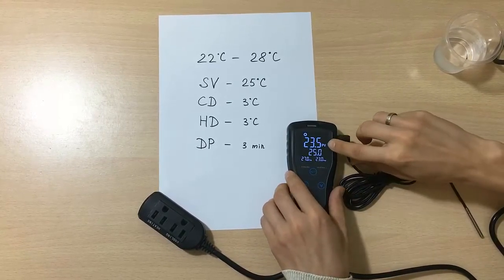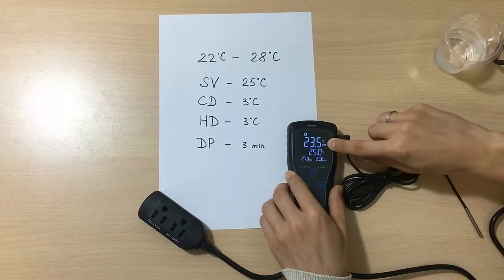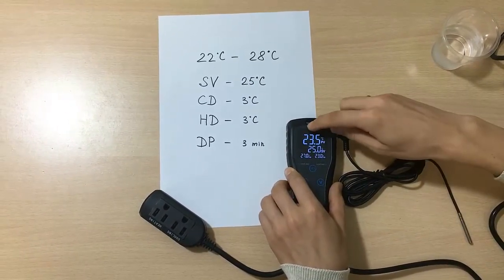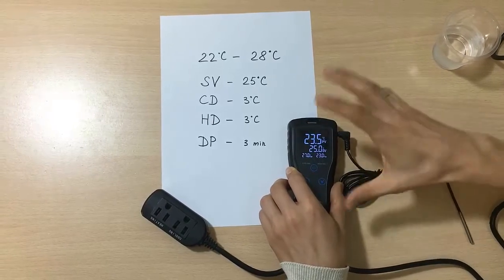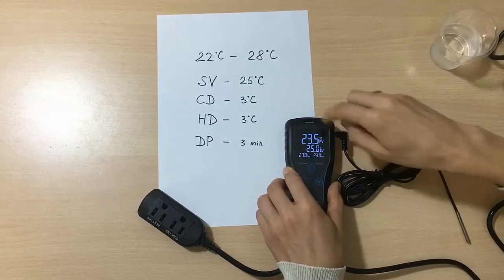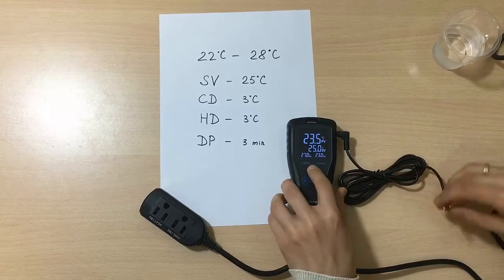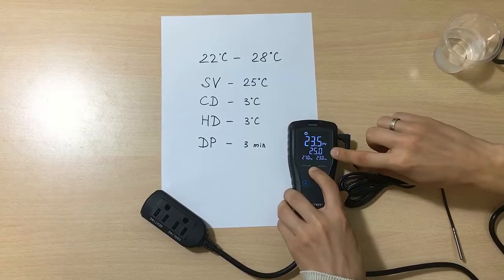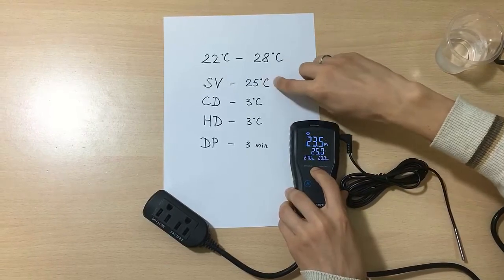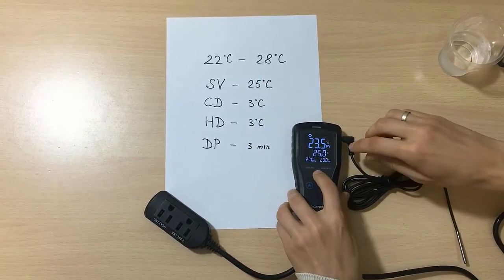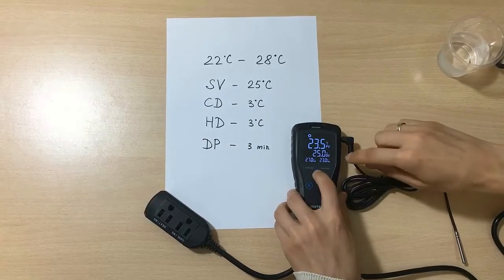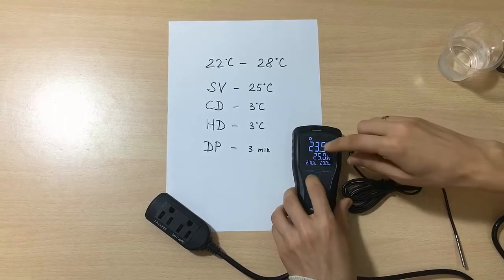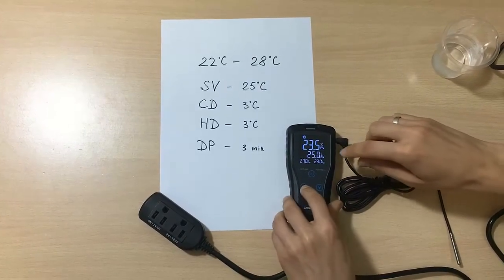So we can change any parameters that you want. First, the PV, as you know, is the temperature that we have right now, the actual temperature on the sensor. As you see, after 10 seconds when I don't do any changes, it automatically exits the setting mode. So I have to press it again. Let's change the SV, which is the set temperature. We have to press the set button and now we have the SV which is blinking here.